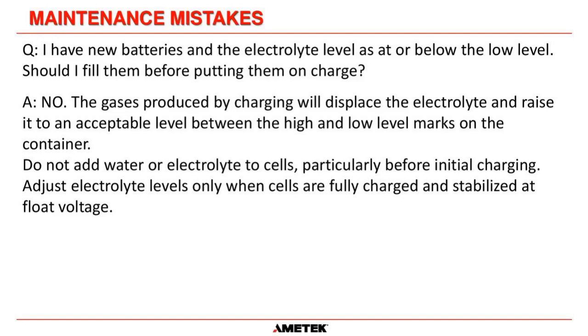The gases produced by charging will do two things. It will displace the electrolyte and raise it to an acceptable level between the high and low level marks on the container. Okay, this is specifically from a battery manufacturer's manual. When you start putting the battery on charge, it creates air bubbles that increase the level. And what it also does is that the lead inside a battery is spongy, and it does draw some of the sulfuric acid into the plates.